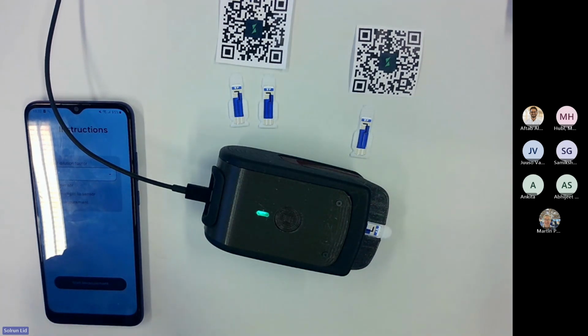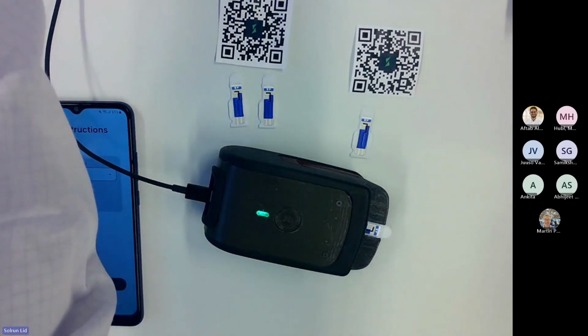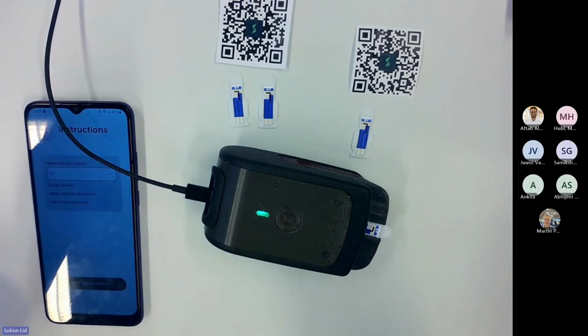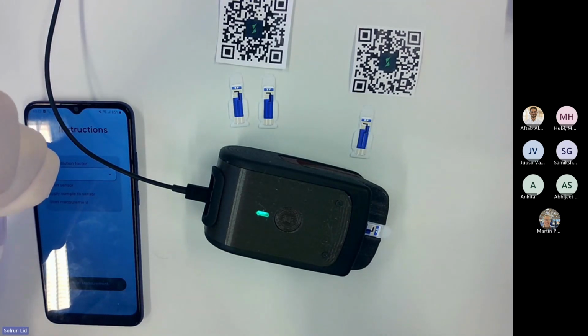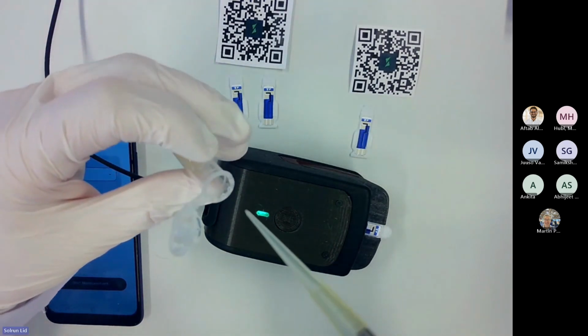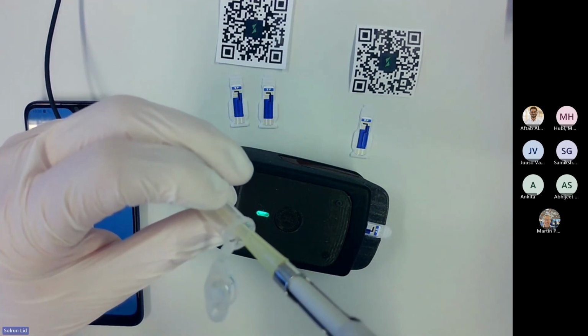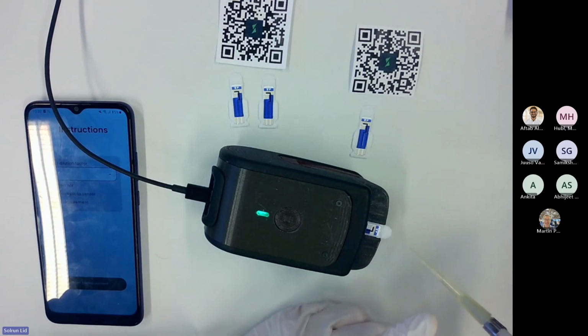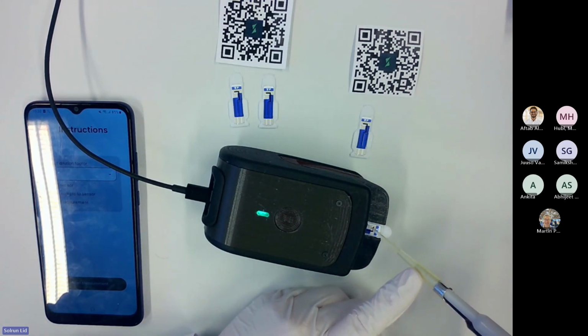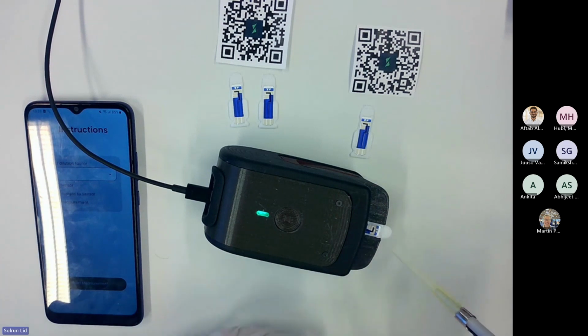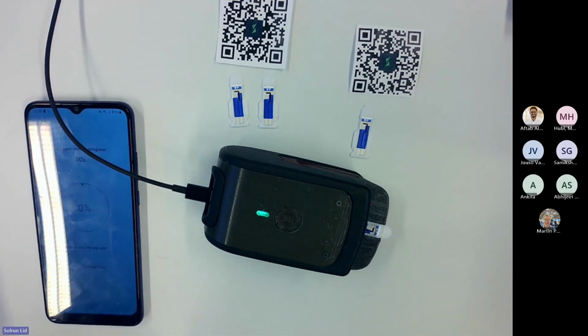Next thing I'll do is apply sample to the sensor. I will apply 50 microliters of the sample that I already prepared, and that is a perfect amount for covering all the electrodes of the sensor. So we want to cover the working electrode, the reference electrode, and the counter electrode. So I'm pipetting 50 microliters onto the electrodes, just like that. What's also very convenient with this device is that it's designed so that in case you spill, it won't go into the device, and it's easy to clean. Okay, so now I will click start measurements.